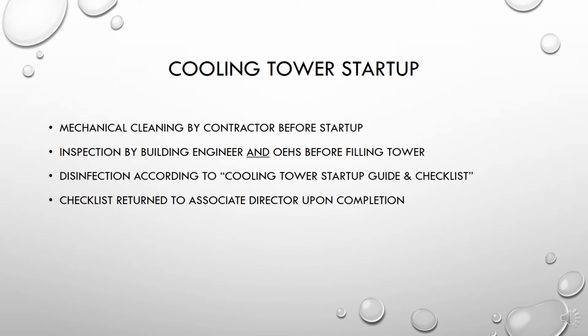So just a reminder for our cooling tower startup, our mechanical cleaning is going to happen from our contractor before we start our startup procedure for the cooling tower. You want to make sure that that cleaning is done. We are starting this week, and we are starting with the housing buildings, moving to Med Campus, and then after that moving on to the rest of campus that has later startup dates.